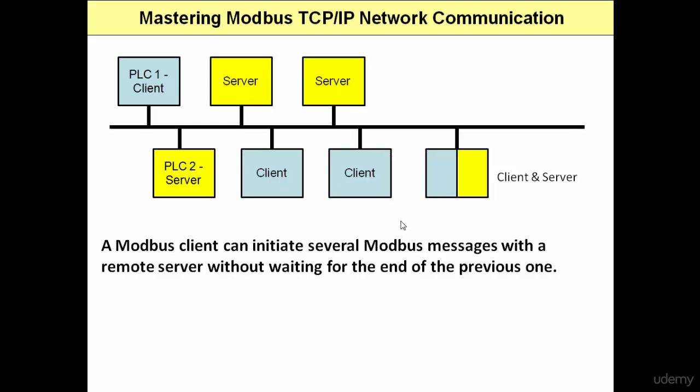and so on. But the way that Modbus TCP/IP is arranged and works is a slight variation from the normal Modbus RTU protocol in the sense that it uses some sort of tagging to actually know what queries match what responses. Okay, so this is a very important property, and it allows much faster communication to take place on the network. So you could exchange Modbus messages between clients and servers much more rapidly than using RS-485.